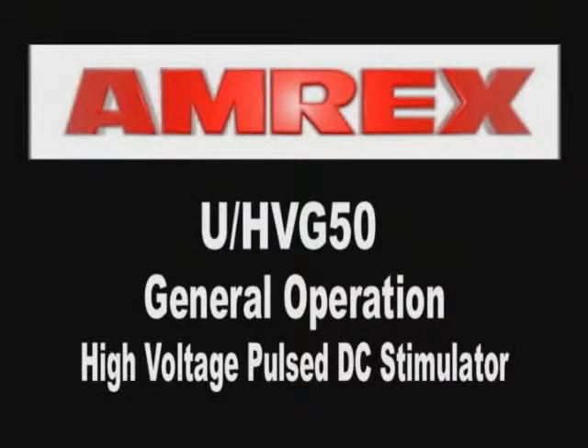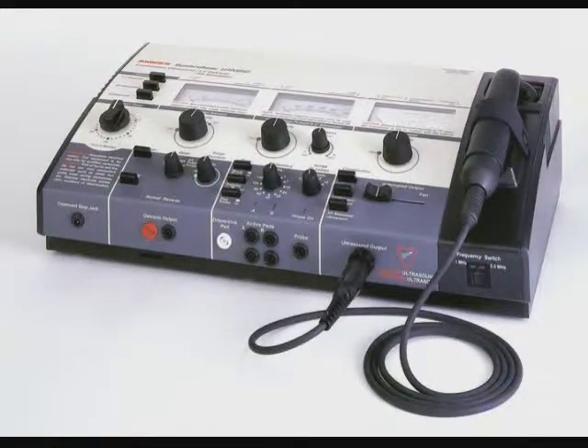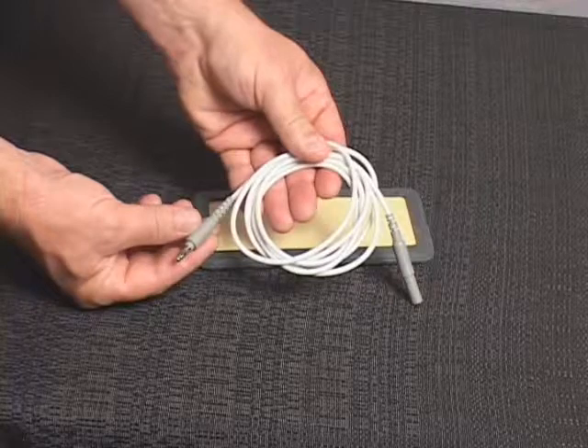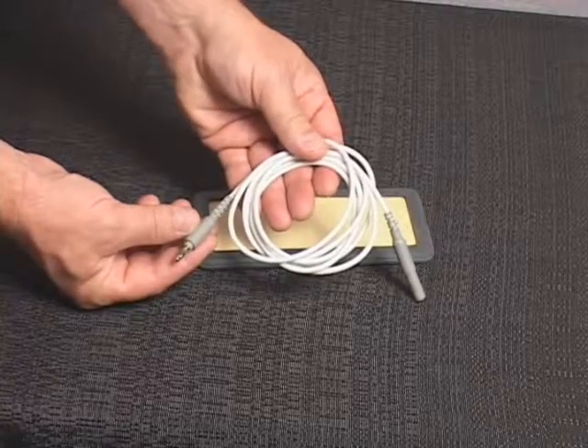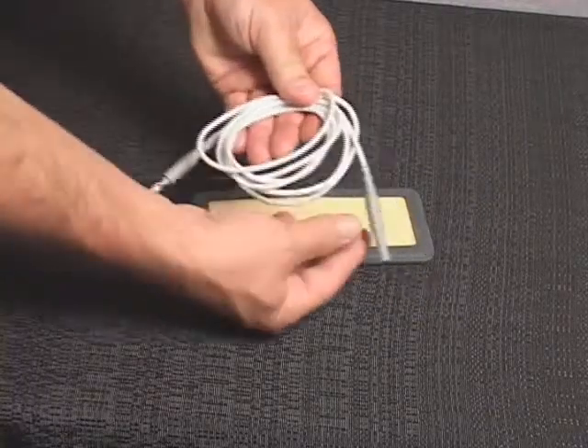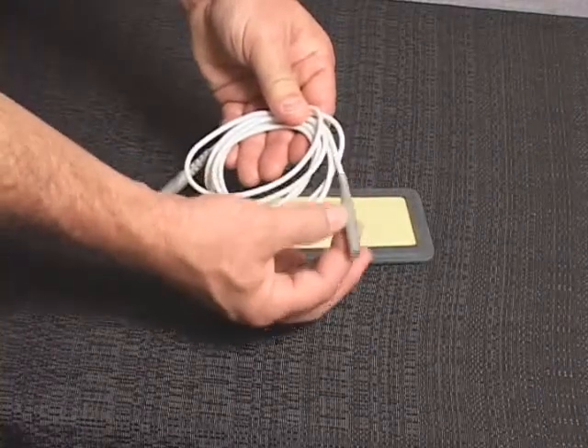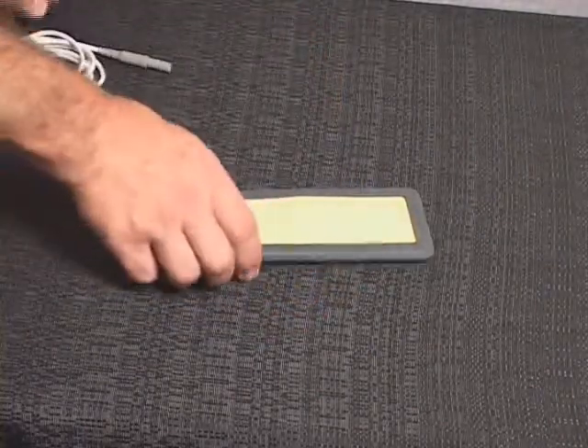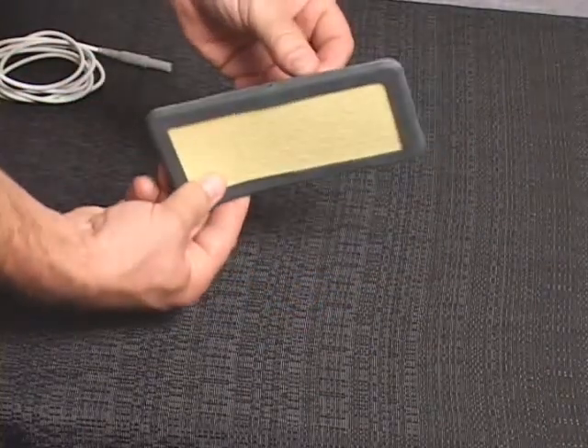HVG50 General Operation, High Voltage Pulsed DC Stimulator. The patient leads should always be checked for proper connection and damage or deterioration prior to treatment. Loose connections or damaged cables can cause low stimulation output, no stimulation output, or sudden irregular increases in output, resulting in possible discomfort to the patient.